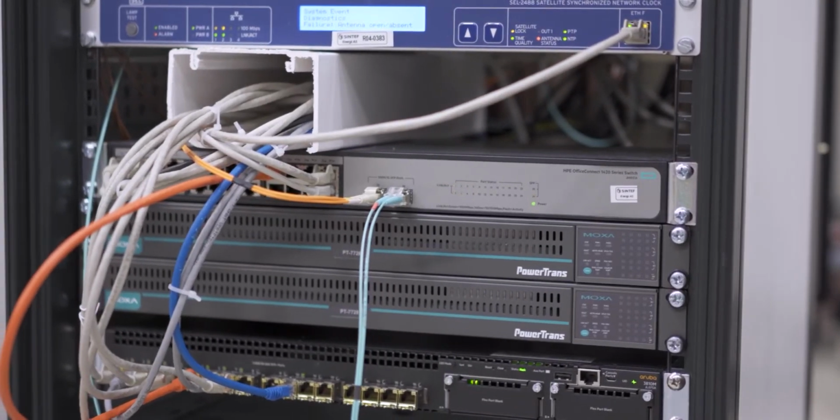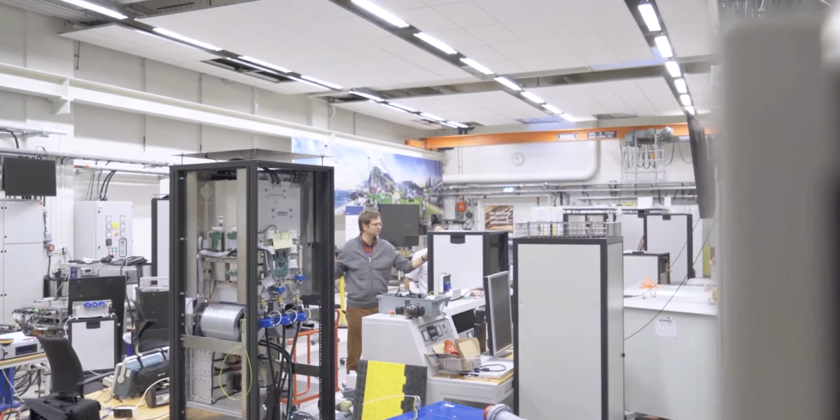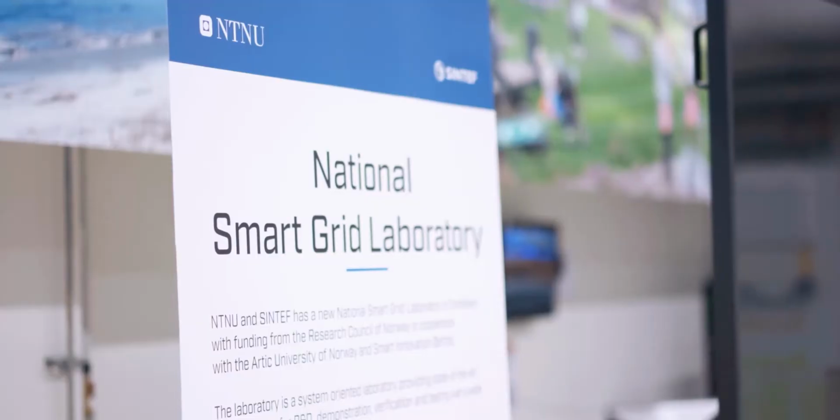So what is a digital substation? It's a substation where devices from different vendors can easily communicate, based on protocols like IEC 61850, and most of the typical hardwire copper connections are replaced with optical fiber cables. If you have a full digital station, as much of the data related to the station will be digitalized immediately. Everything from measurements, control, and status reports. And the exchange of data is through digital services. And the functionality of the station is first and foremost through software.